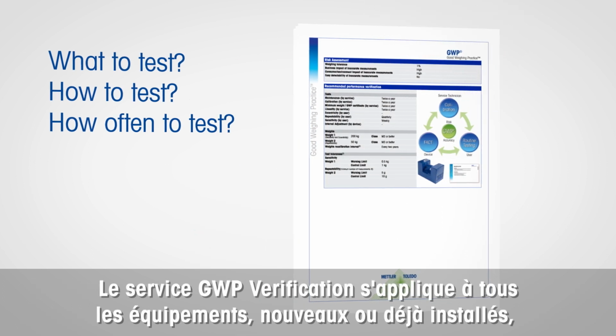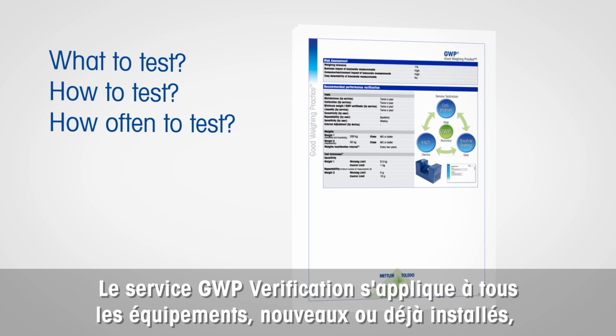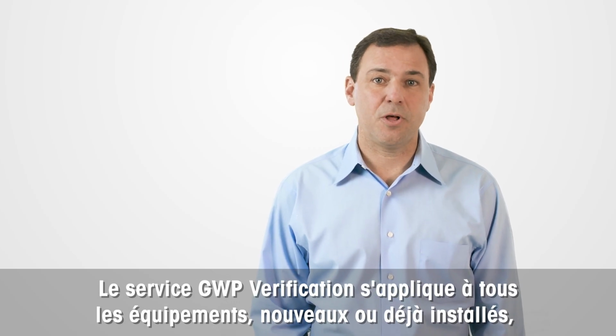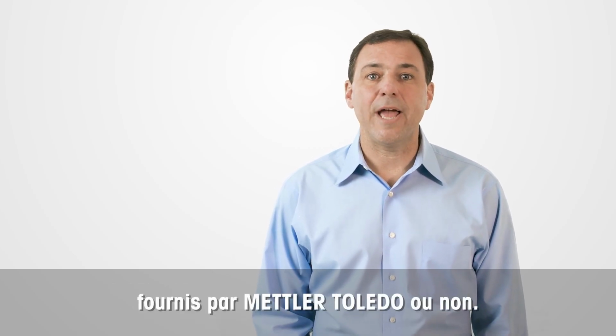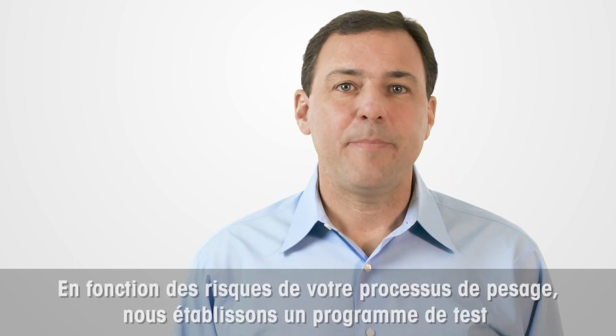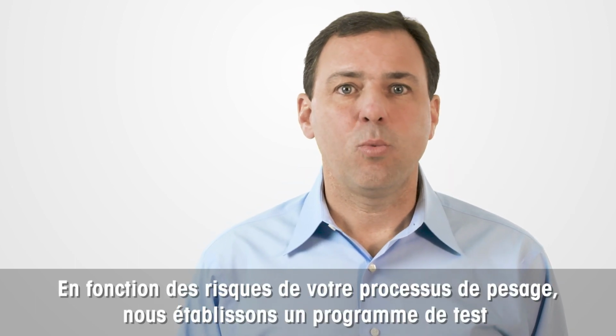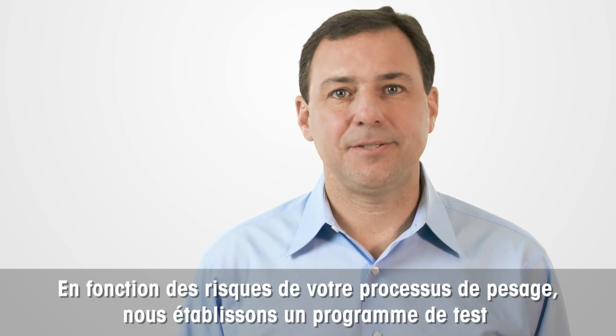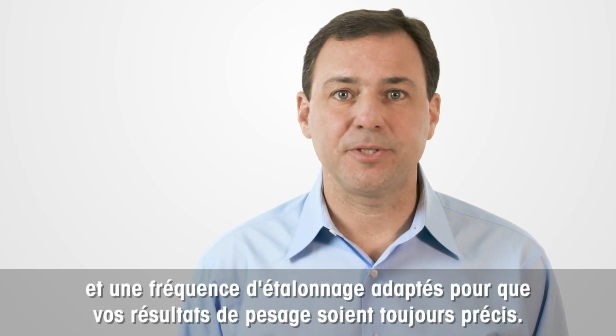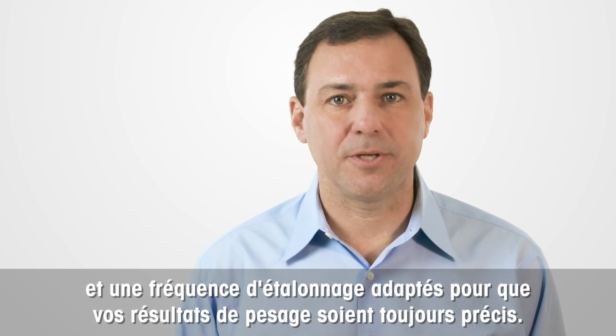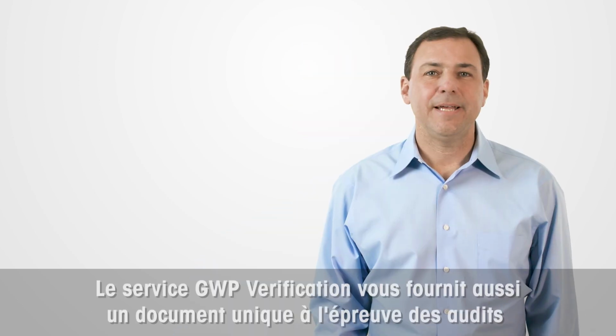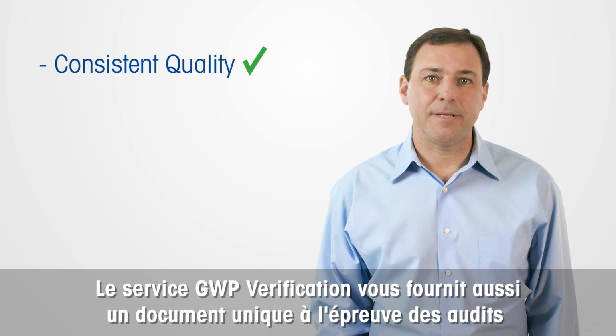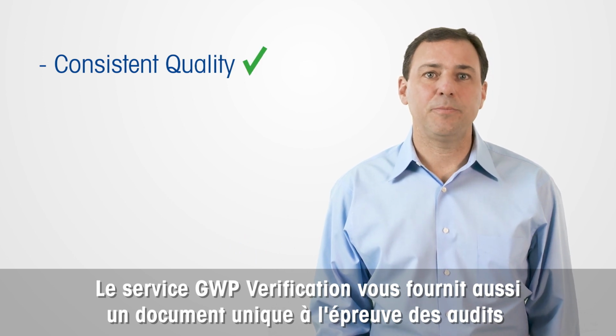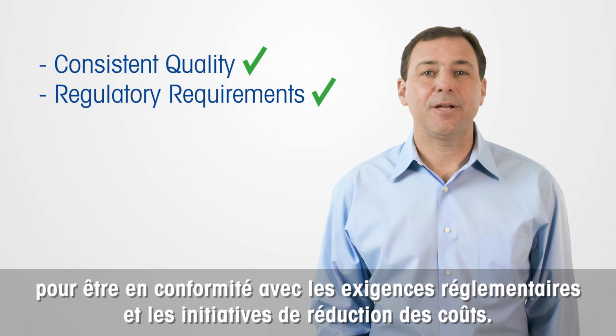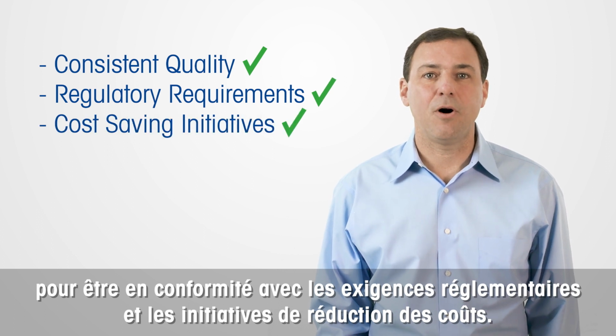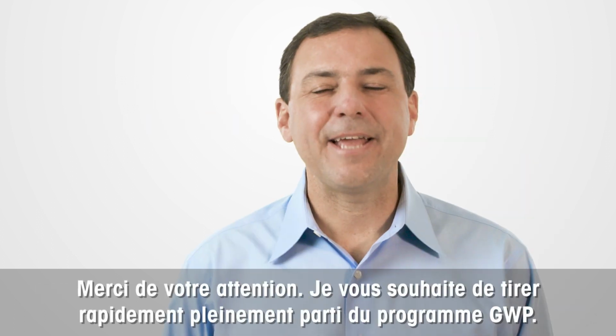We can perform GWP verification on all equipment, whether it is new or already installed, METTLER Toledo, or any other manufacturer. Based on your weighing process risk, we will establish an ideal testing program and calibration frequency to assure accurate weighing results at all times. In addition to maintaining consistent quality, GWP verification will help you meet regulatory requirements and cost-saving initiatives with one audit-proof document.